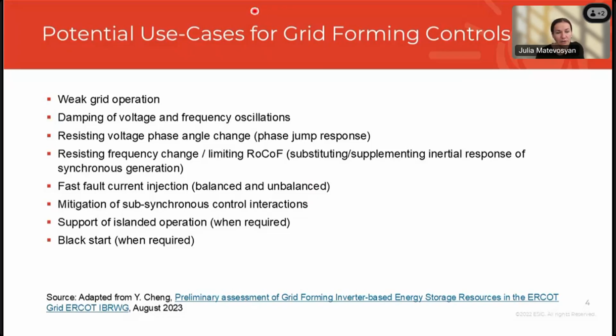Fast fault current injection for balanced and unbalanced faults, mitigation of subsynchronous control interactions, support of islanded operation when required, and black start operation when required. So the first few functions are seen more as core functions of grid forming, whereas the last two are more optional and system specific.